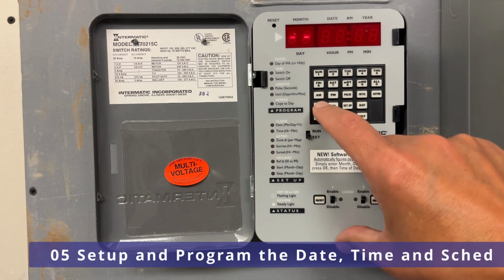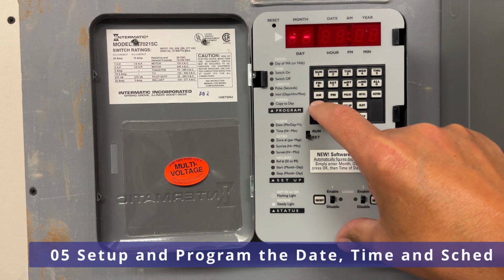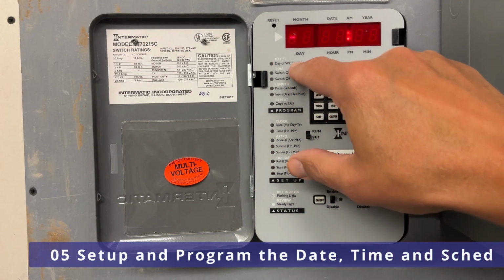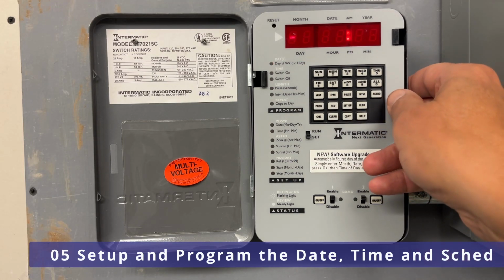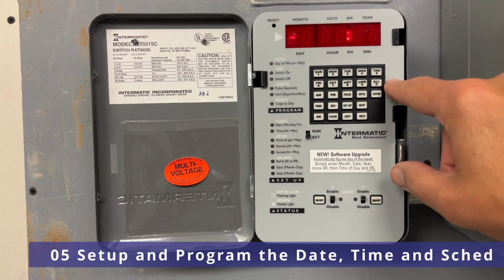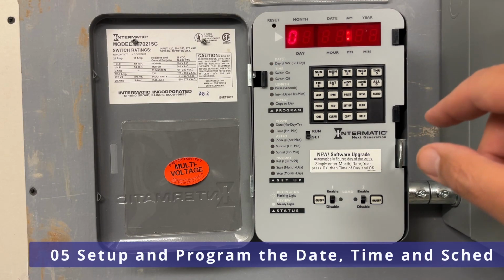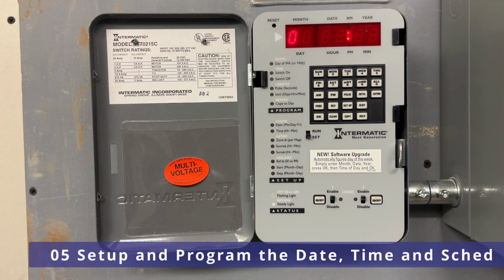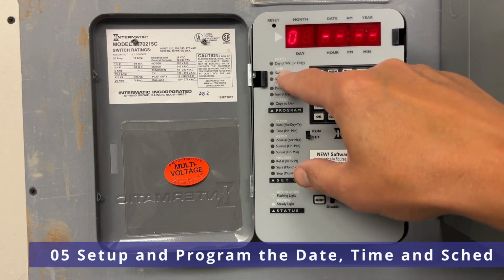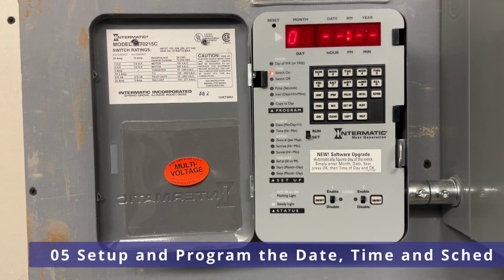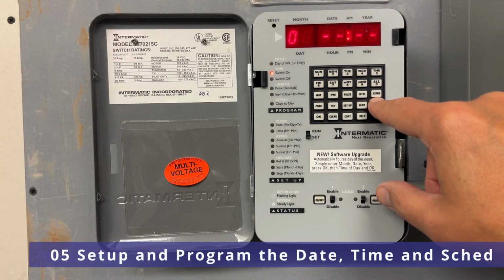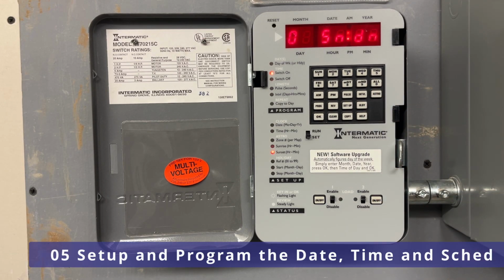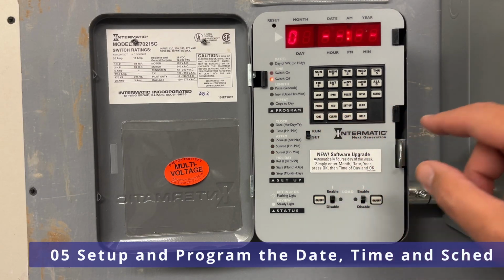This is when we go ahead and hit the program key. And you'll see it's asking us for the day of the week. So now our day of the week for us is going to be 0, because that represents all of the days, and we hit OK. And then the next thing we want to do is, when do we want it switched on? We want it when the sun goes down, so we press our Astro button, which is sundown, and we hit OK.